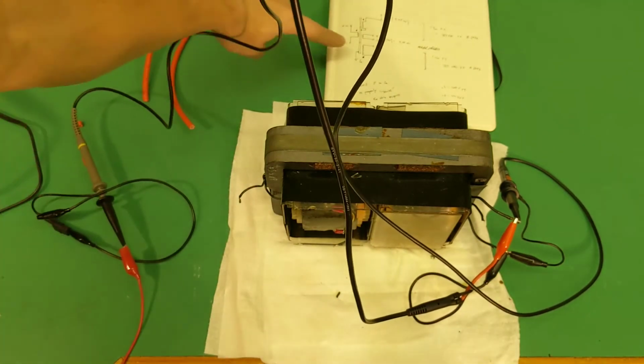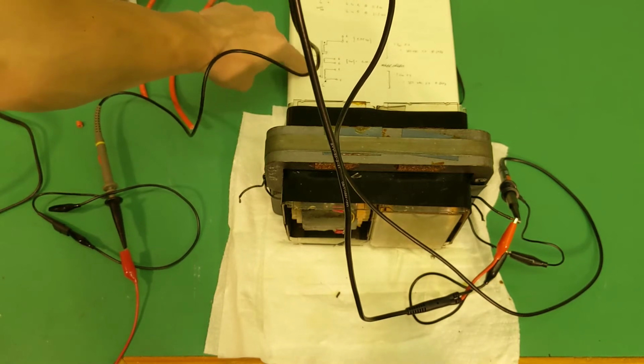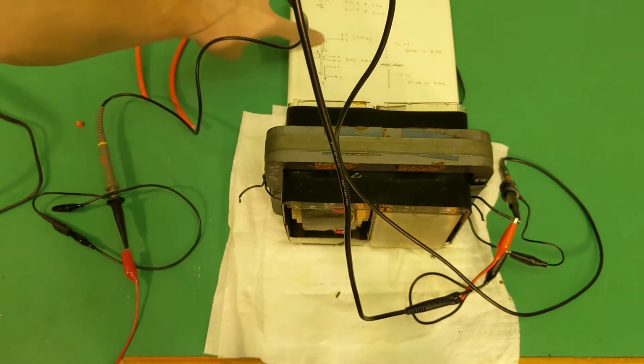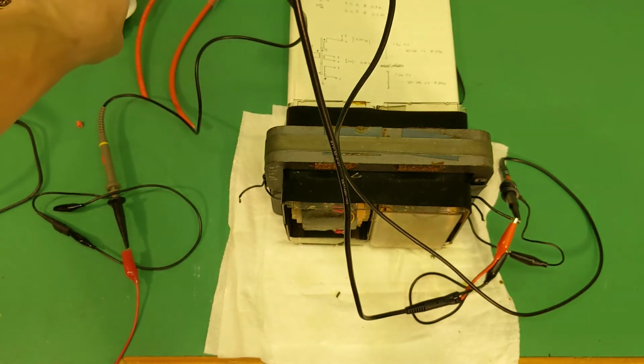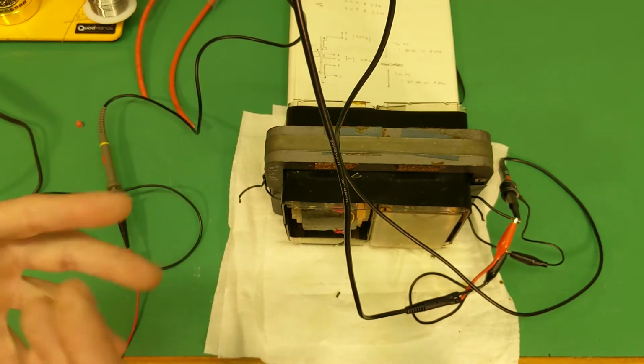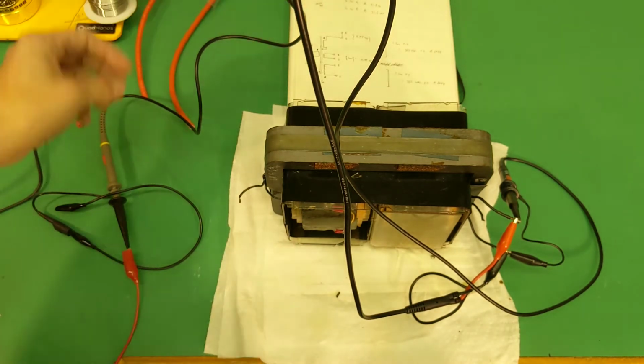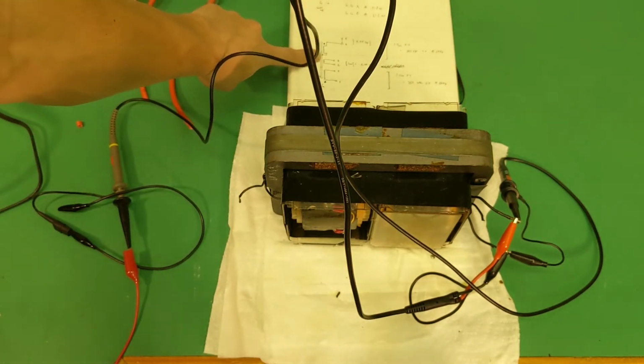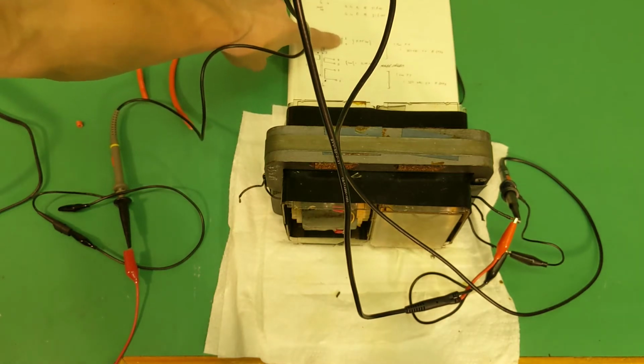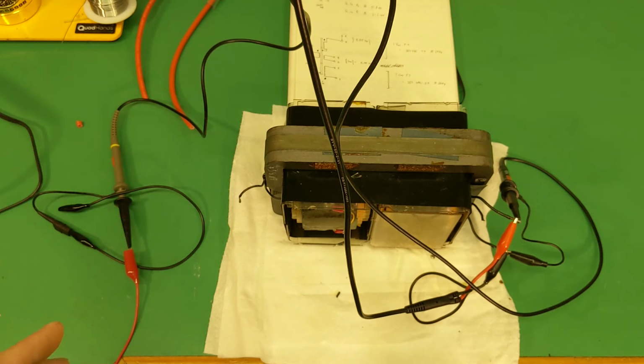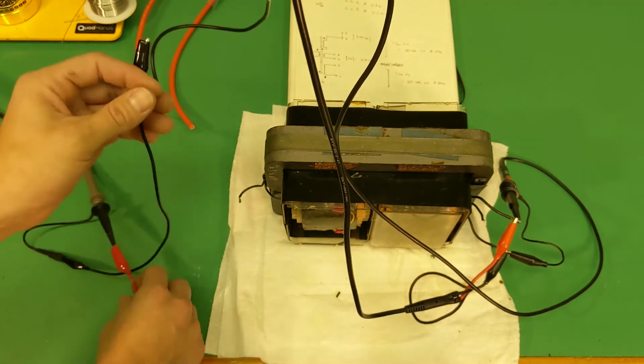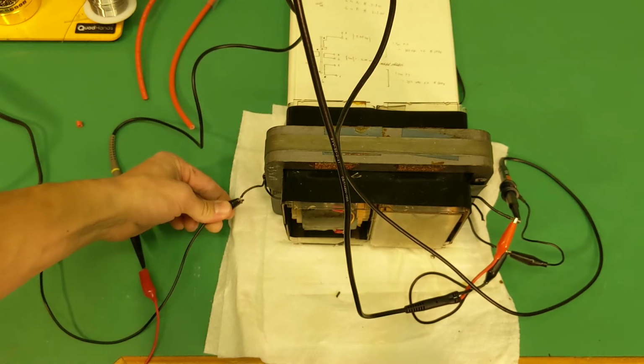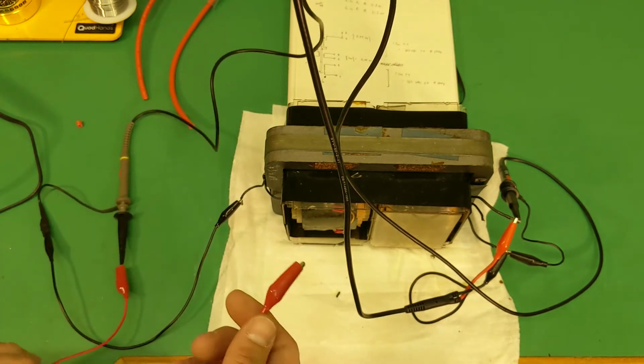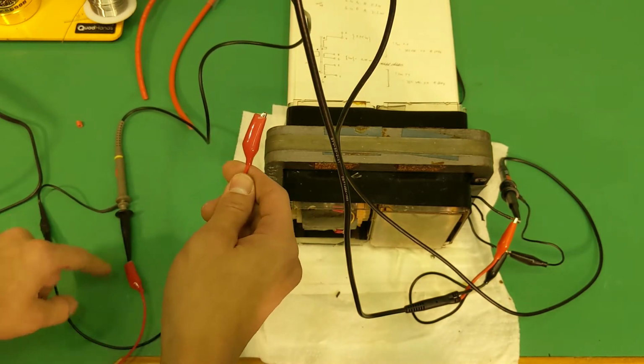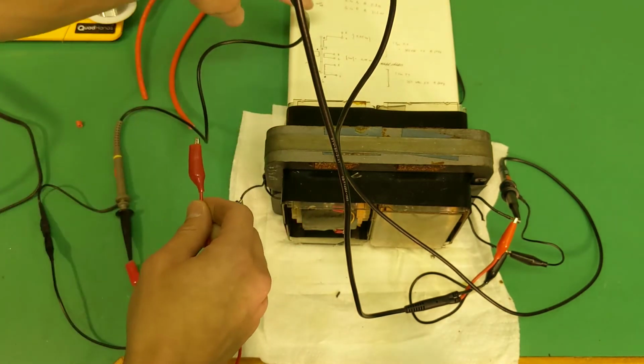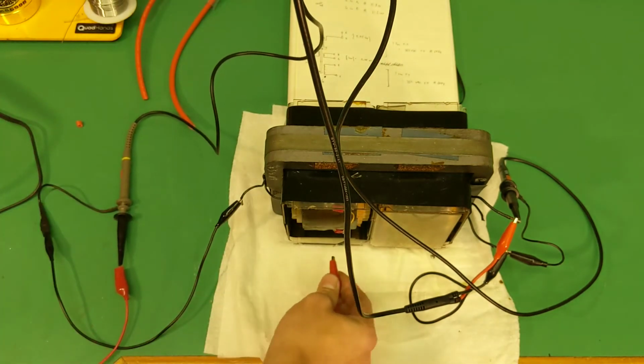Looking at our schematic, we need to test each winding as drawn and see what output we actually get with the 1 volt input. I'll start by connecting the ground point to terminals A and D, since we think that's one of our high voltage windings based on initial analysis. I'll connect the probe ground to the center tap, and the probe connection to A or D — I'll connect to A, right here.